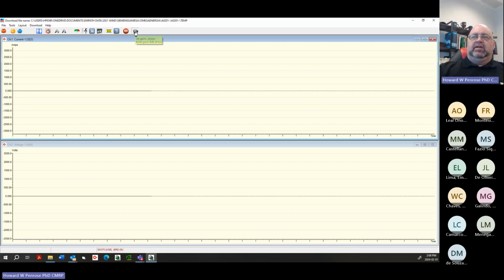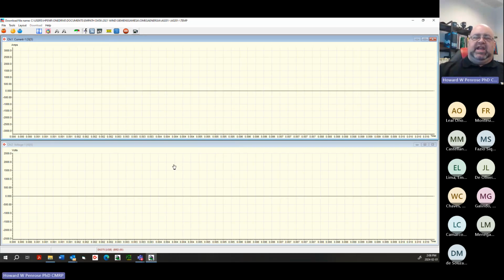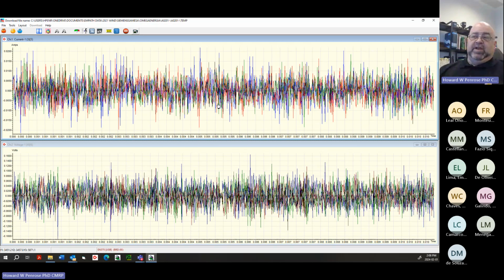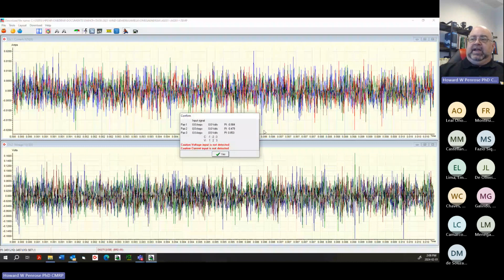F8 or this button will adjust the gains in the instrument, and will also help if I have something out of place or backwards. It's going to show me the RMS current, the RMS voltage, and the order of my current probes in relation to my voltage probes - phase 1, phase 2, and phase 3. Sometimes those might flip. And then I watch for my power factor. That's the third one.